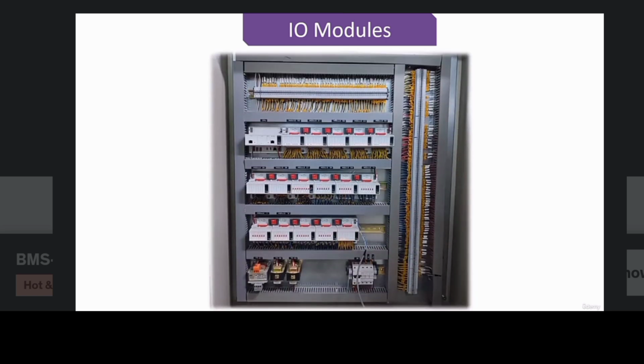Here is an example of a DDC panel from one of our projects. This is a DDC controller which doesn't have any I/O points. So, we have used expansion I/O modules which are connected to this DDC controller using a communication bus. You can see that all these modules are connected in series, and then they are connected to the DDC controller, and they are communicating to the DDC controller using a communication protocol.